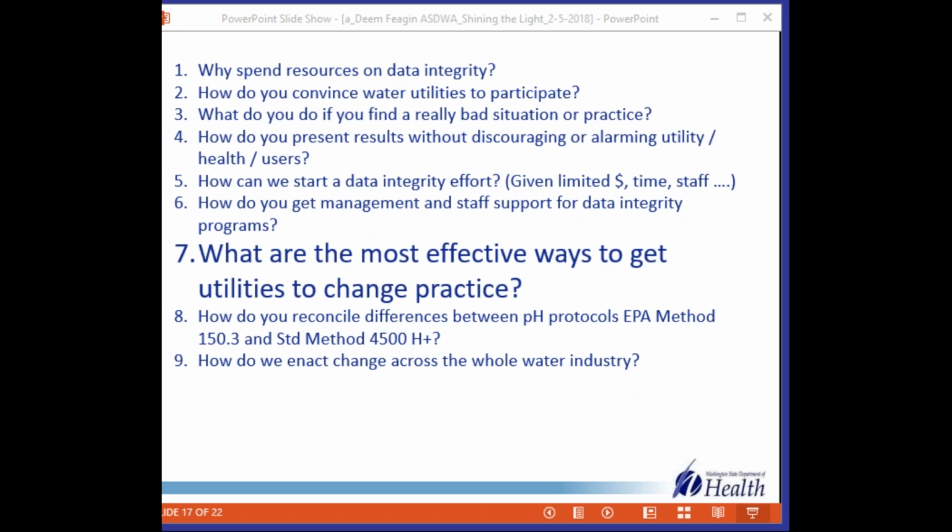I would have to say that is a typical health department approach. Let's just be conservative and slap on an 8% operating correction. But since I knew I'd be talking to you guys today, it seemed difficult to really justify. So we came up with a different approach, and that was to pull back the treatment plant's operations from the edges of that operating envelope. So instead of going up to the very large number, just operate below that number by a significant amount until you can resolve what the issue is or how big the inaccuracy is. So it invokes a different approach than, let's just be conservative.